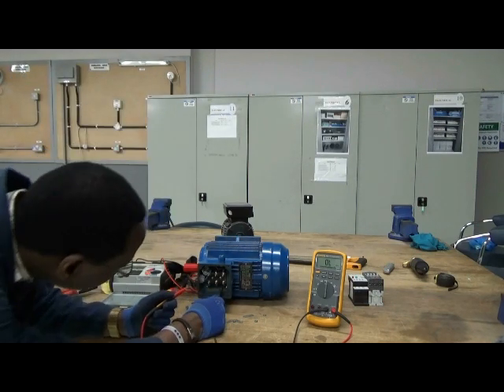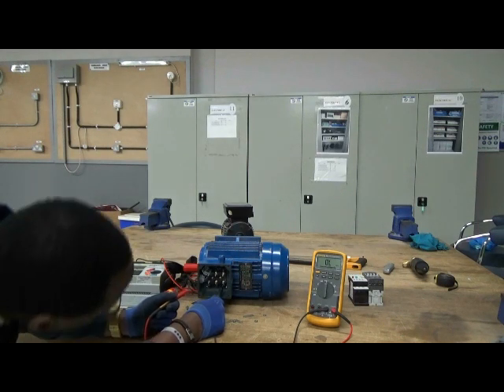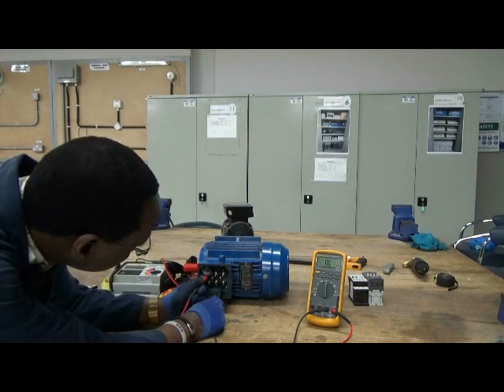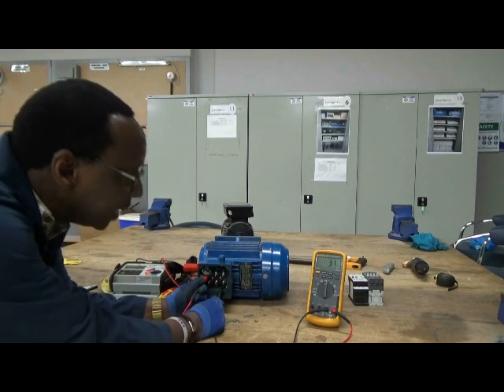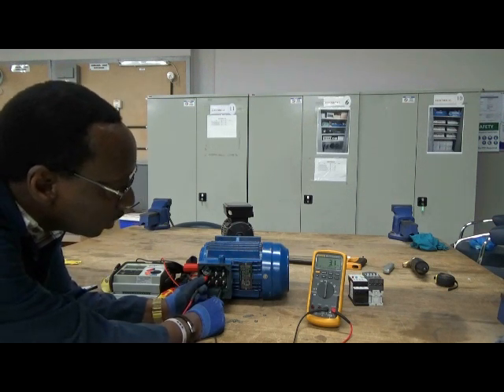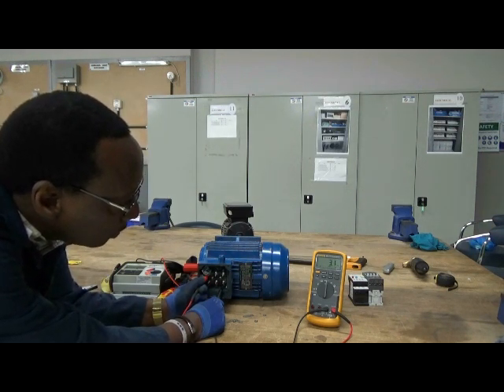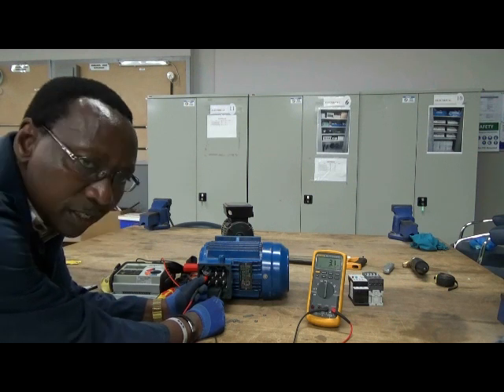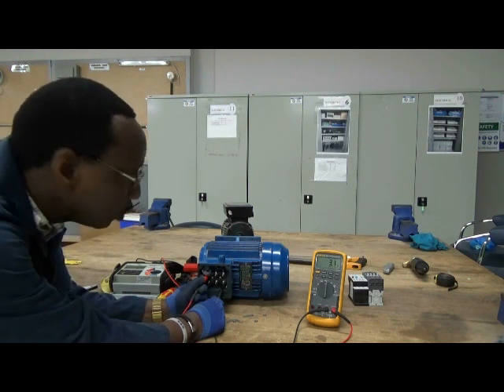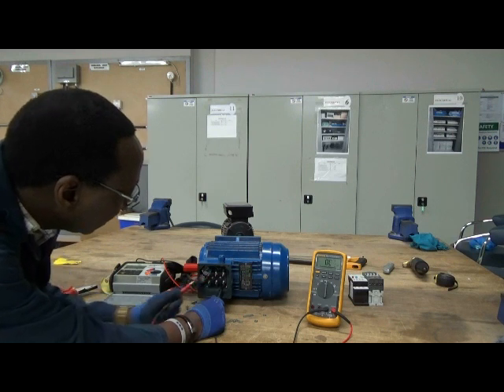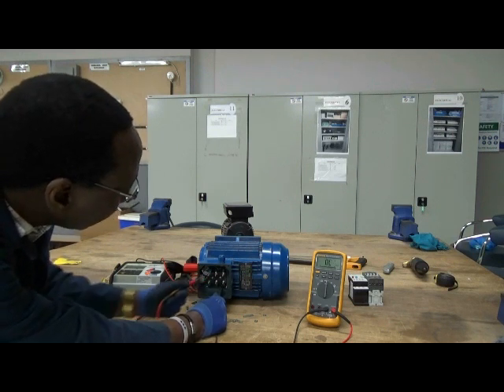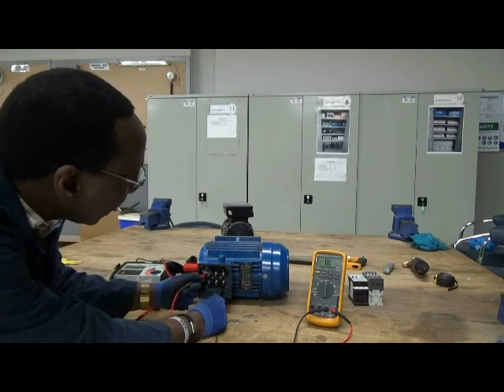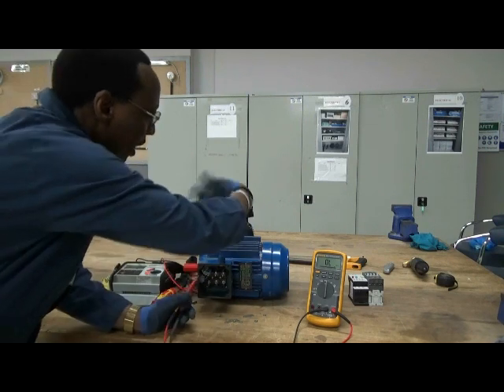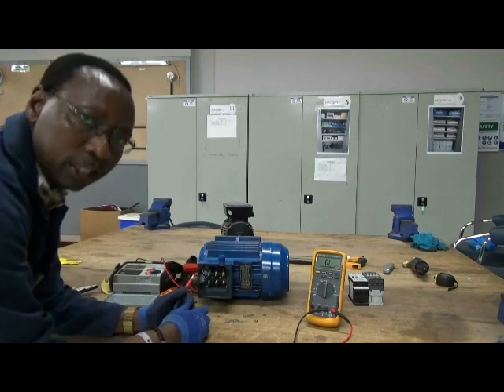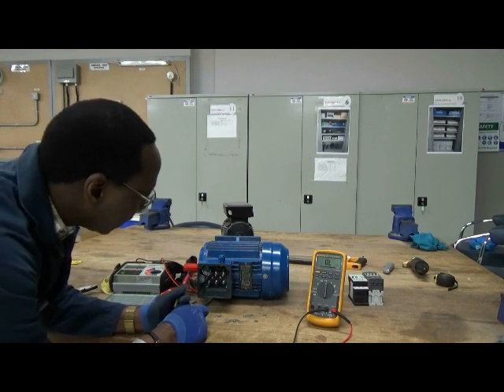I'll put one point there, and another one I'll put on the last one. And if you can see that well, there's 3.1 ohms. That is the resistance of the first winding. So it means this point is probably the beginning, and that one is possibly the end. And the winding has been done right round inside the stator winding to produce that.